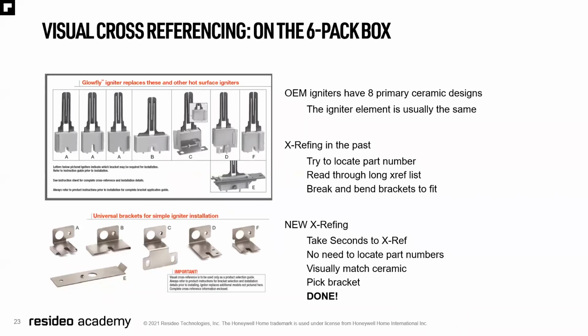OEM igniters typically have 8 primary ceramic designs. The element doesn't change that much. What changes is how it mounts to the furnace or the brackets that it can use. So in the old days, if you had to do a cross-reference, you had to locate the part, read through the list, then you had to take your bracket and either bend or break it to make it fit properly in the furnace. With the Glowfly, you just read the sheet and it tells you which one to use. If you're using the A, B, C, D, E, or F bracket, just install it. Most technicians never even refer to it. They just use their eyes and pick the right bracket.